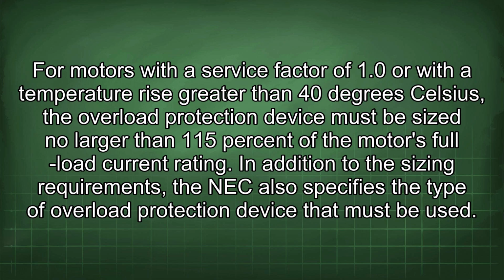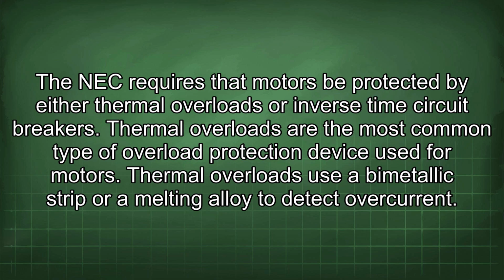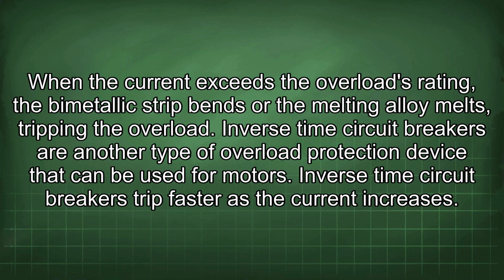In addition to the sizing requirements, the NEC also specifies the type of overload protection device that must be used. The NEC requires that motors be protected by either thermal overloads or inverse time circuit breakers. Thermal overloads are the most common type of overload protection device used for motors. Thermal overloads use a bimetallic strip or a melting alloy to detect overcurrent. When the current exceeds the overload's rating, the bimetallic strip bends or the melting alloy melts, tripping the overload.